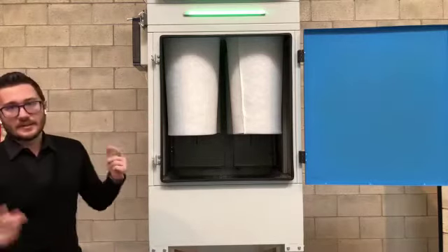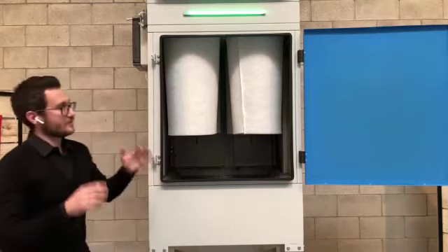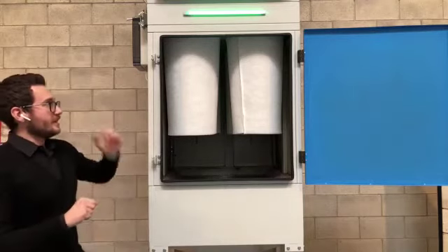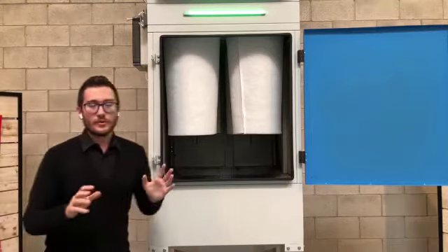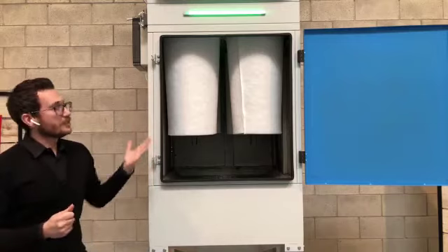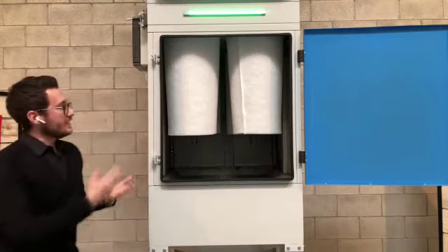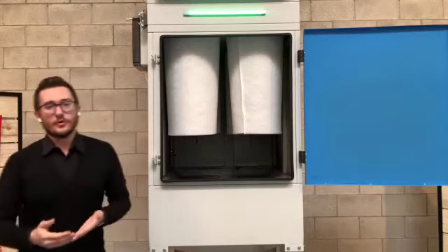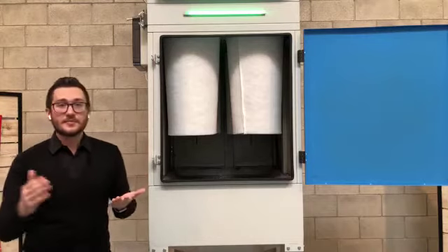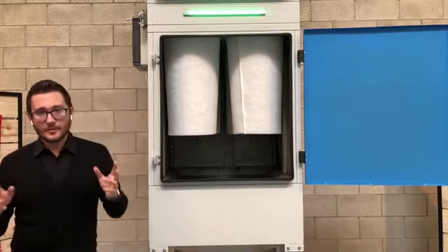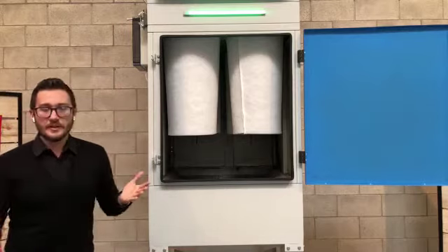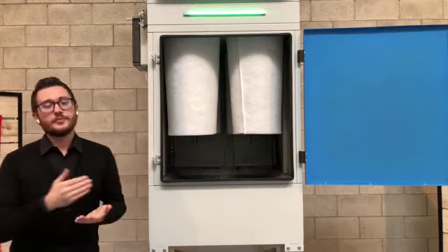Last thing, but not the least, I would say, which is really important always from a maintenance point of view, is the DP LED. I didn't mention the DP LED, which is one thing that personally we always suggest, because it can give you the idea of the state of the filter. This DP LED works according to different steps of, let's say, alarm. I will call it alarm now. Why? Because you can have here from green to red. How does it work? It works according to the pressure differential.